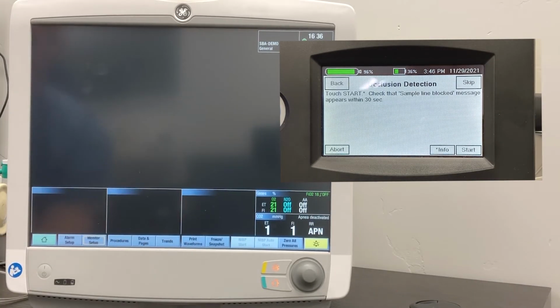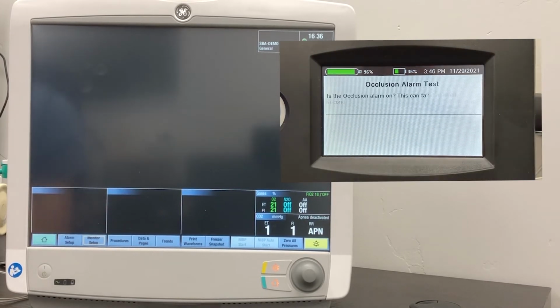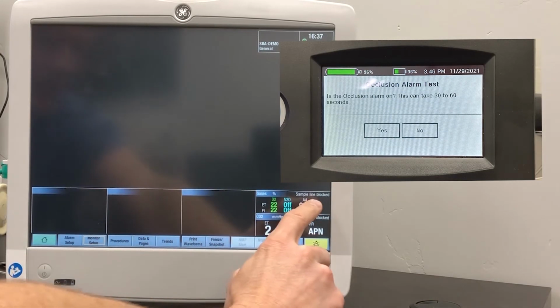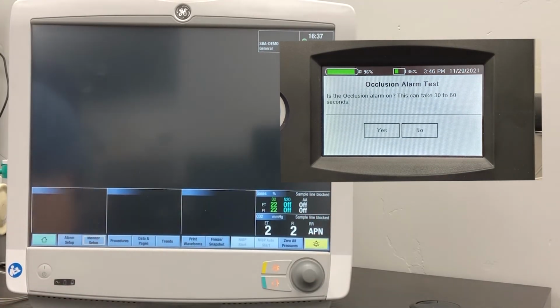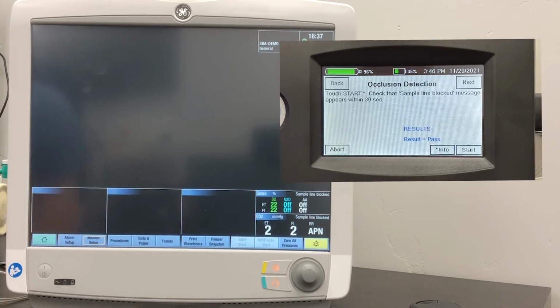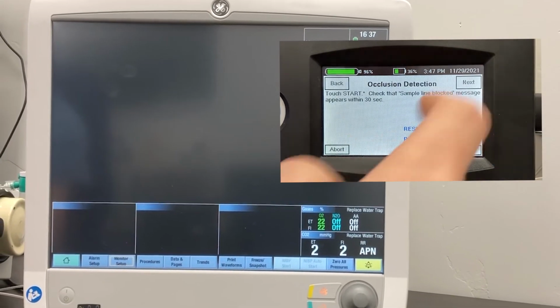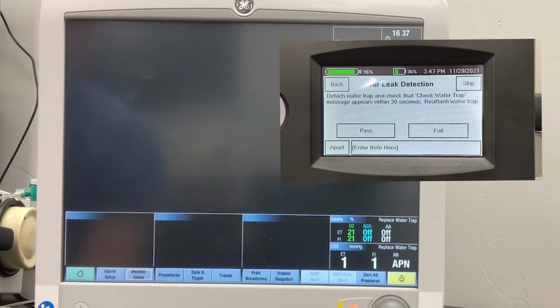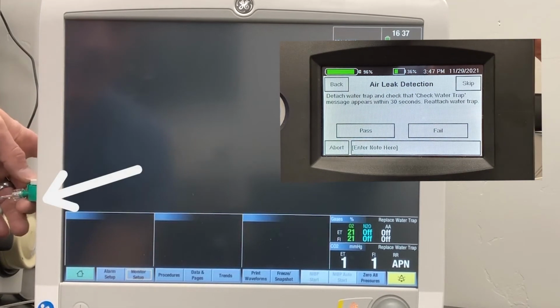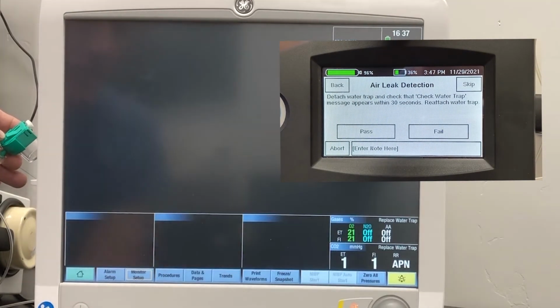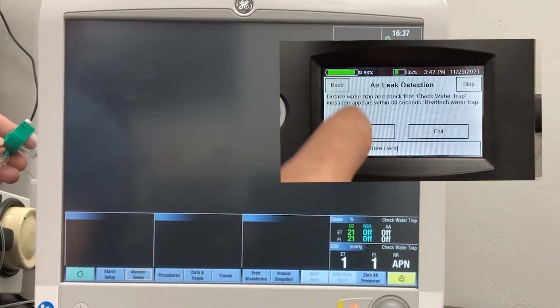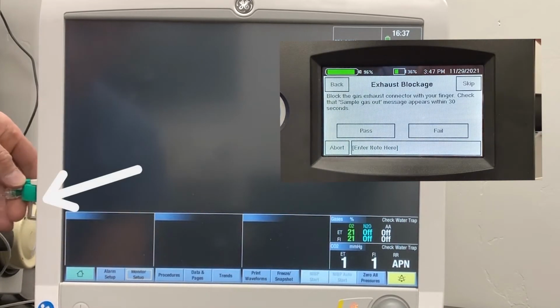Okay, to do the occlusion detection, we're going to press start, which will occlude the sample flow line. And we watch over here, you can see it says sample line blocked. So now we can hit yes. That's a pass result. Next we will detach the water trap. And we'll watch over here to make sure that it gives us a message of check water trap. There it is. So that's a pass. We can plug the water trap back in.